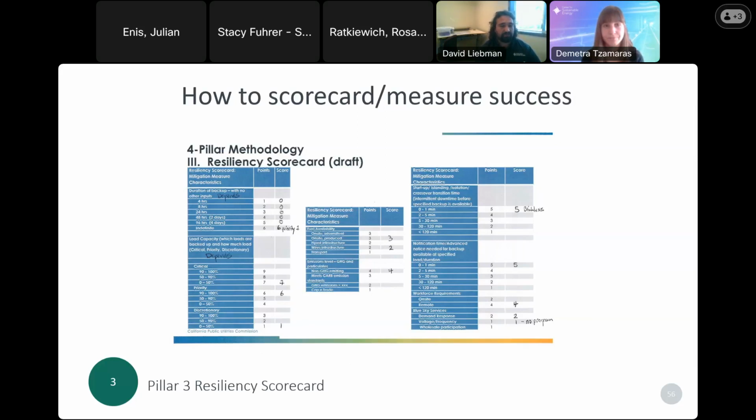But we found that for the most part, if we load shed to 50% of our critical loads, we could serve those. We could serve pretty much all of our priority loads, depending on our load shedding flexibility. And then we really can't serve our discretionary loads. But again, it depends on the time of the year, and whether we are in a summer session, or in a fall semester experiencing a really extreme heat day, where all of our buildings are having to cool. That really determines how much of the entire campus we can support.